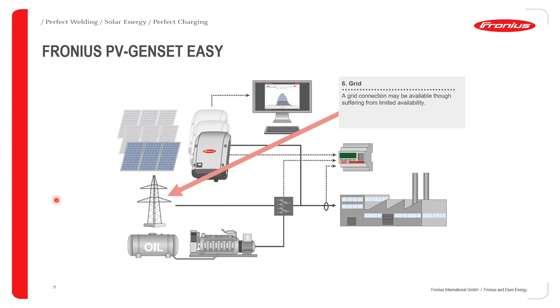When the grid is online, the diesel genset is switched off and the PV inverters assist the grid, decreasing the energy drawn from it. With this controller you can also set a zero feed-in limitation — many municipalities in Africa do not allow grid feed-in — so the Fronius PV controller can enforce that limitation to prevent any back feed to the grid.